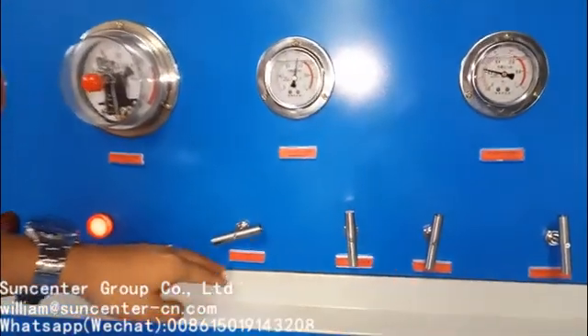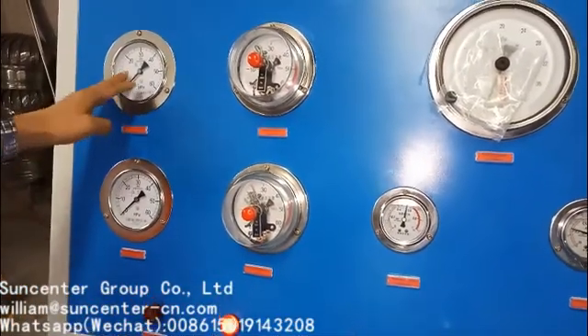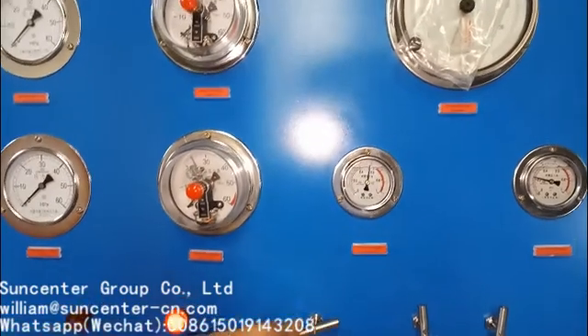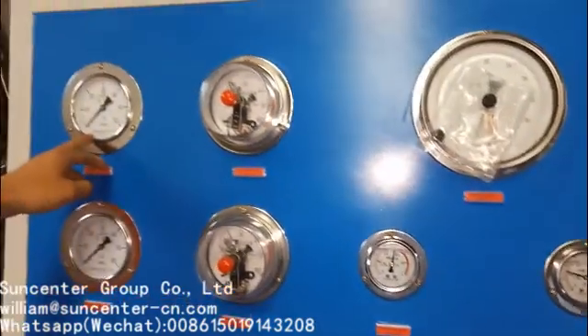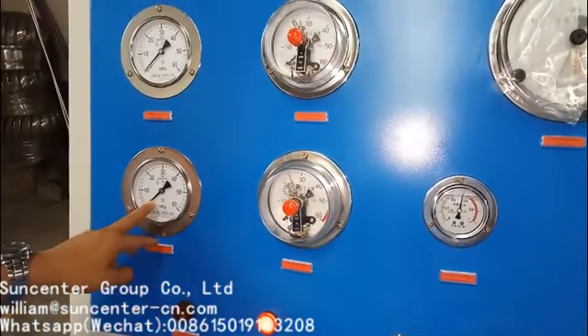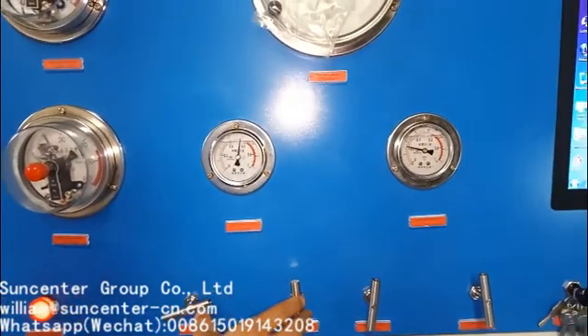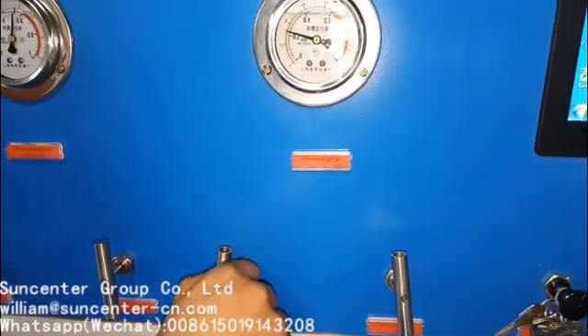If you want to calibrate pump one, you can open this valve and use this pressure gauge to calibrate. If you want to calibrate the other pump two gauge, open this valve. Normally close the two valves. The other unloading valve is normally open — you do not have to regulate.